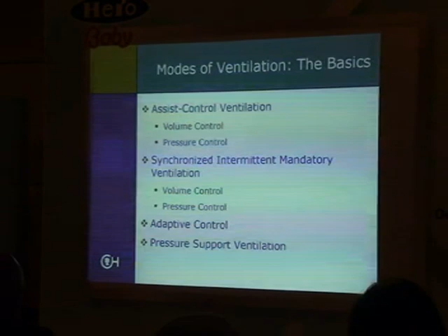So for assist control modes, this is full support on the ventilator. Every single breath, even if the patient initiates the breath, is a full supported breath. Fully controlled inspiratory time, fully controlled how much pressure, how much volume, depending on how you set. If it's set as assist control volume, then you're setting the volume and you need to be monitoring that pressure to make sure the pressure doesn't get to be too high. If you're set as pressure, then we want to be monitoring the exhaled tidal volume to make sure that the tidal volumes aren't too high or too low. If your compliance starts to change in a pressure mode, your tidal volume is going to drop and start to go too low.